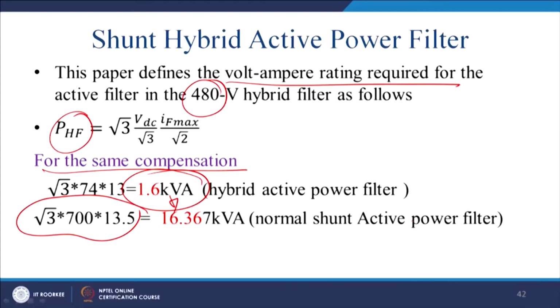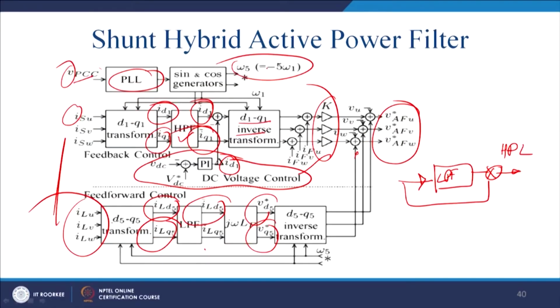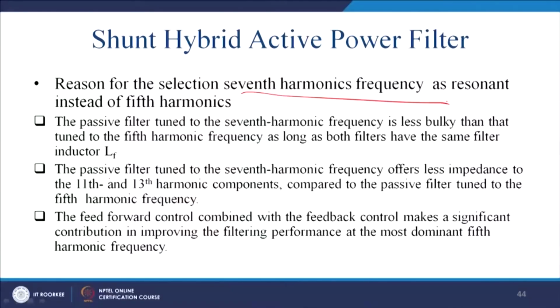Why not do this instead? You can go back to our block diagram. This has been designed for the 5th harmonic, and we can do the same thing for the 7th harmonic, and thus your filter is required to be designed for the 5th harmonic. It has been found that if you design for the 5th harmonic, the system will be more bulky and costlier, and for this reason the 7th has been found to be the more optimal solution. And so, the resonance frequency of the passive filter, as you know, is 1 by under root of LF into CF. So, reason for the selection of the 7th harmonic is as follows.